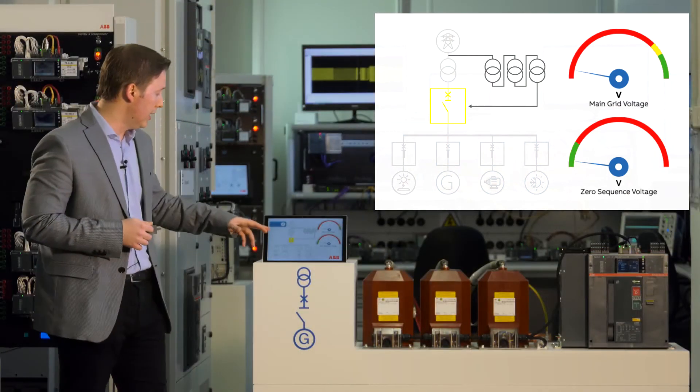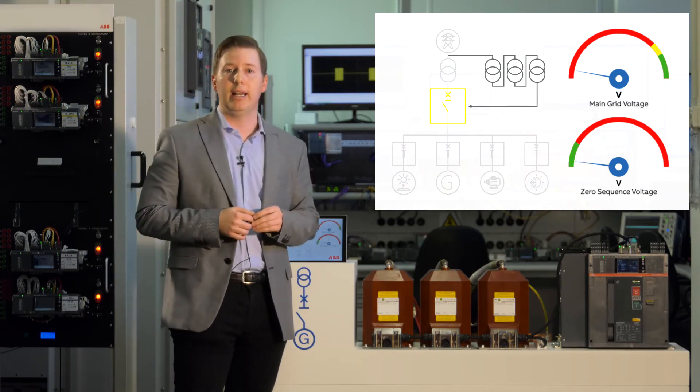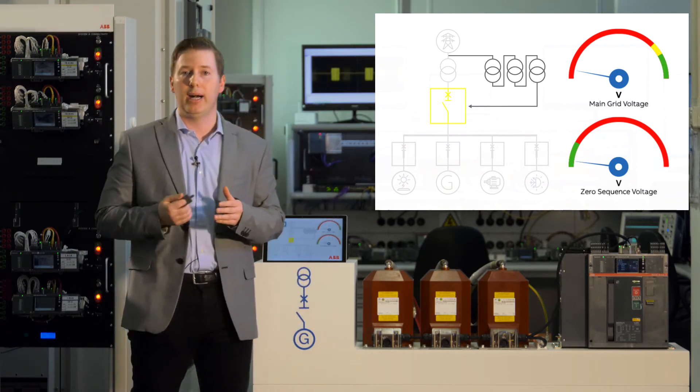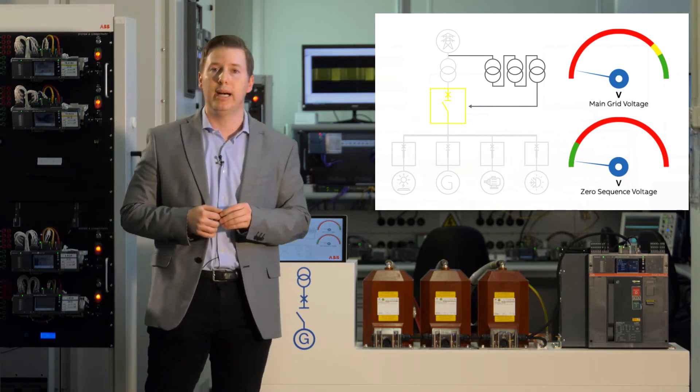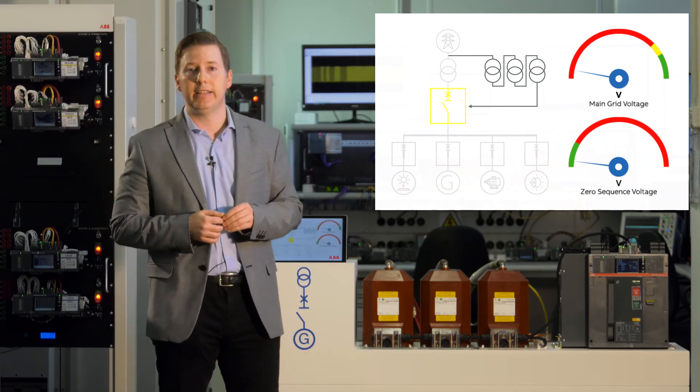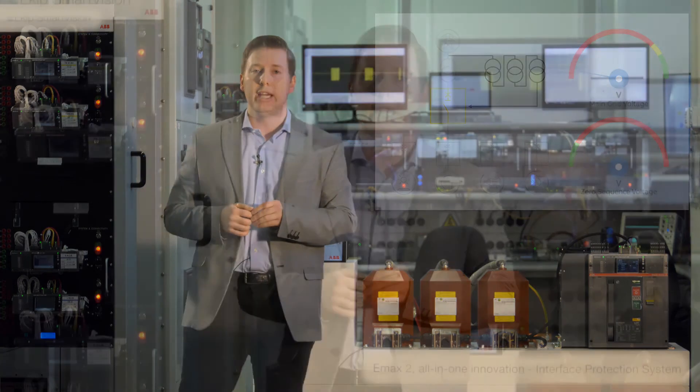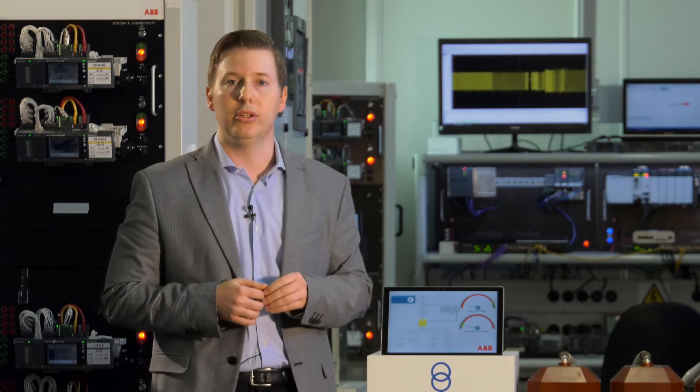As you can see, we have the shutdown of the whole plant since we have an imbalance between the power generated by the local generation and the power consumed by the loads. In order to maintain active the local plant, we have to implement the other feature called load shedding in order to maintain the balance between power generated and consumed by means of a rapid disconnection of the so-called non-priority loads.